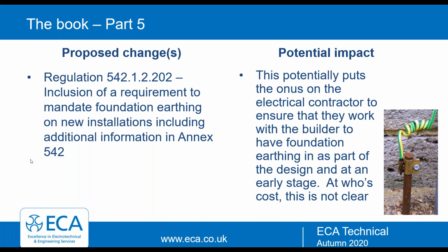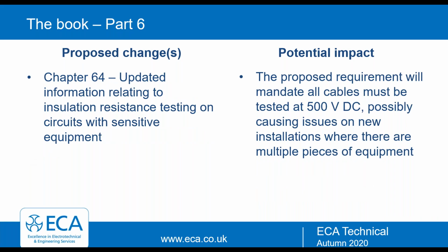Next slide please, Omar. So that should take us out of part 5 and into part 6 now, inspection and testing. Not masses have changed, but one thing that has updated is about insulation resistance testing on circuits with sensitive equipment. It may not impact many, but it might impact some. It emphasises that all cables must be tested at 500 volt DC. Now, we've always done 500 volt, haven't we? Or has there ever been any exceptions?